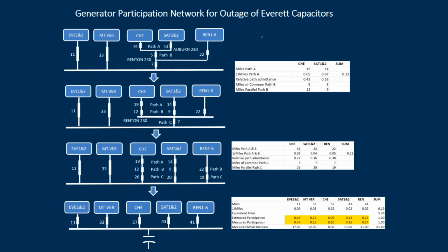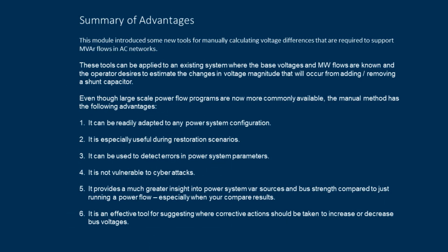So this is a very powerful and easily updated tool. If, for example, our Renton units were offline and our Satsop units were offline, there'd be no path sharing. In that case, my relative length for Chehalis would simply be the 19 plus the 5 plus the 7. And so I can very easily update these diagrams depending upon which generators are in service or which generators are hitting their megavar limits. So this module has introduced some new tools and concepts for manually calculating voltage differences that are required to support megavar flows in AC networks.